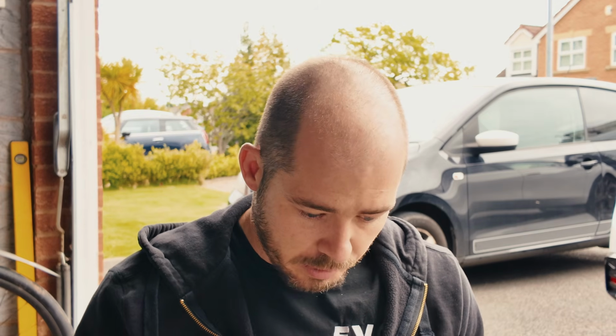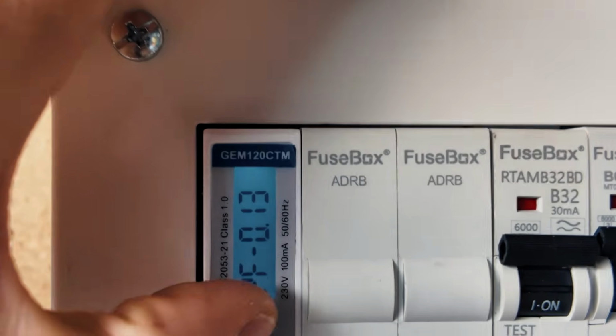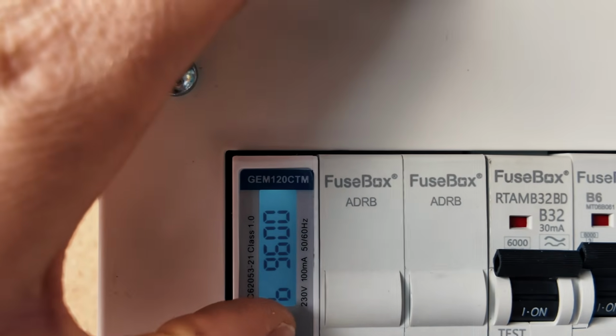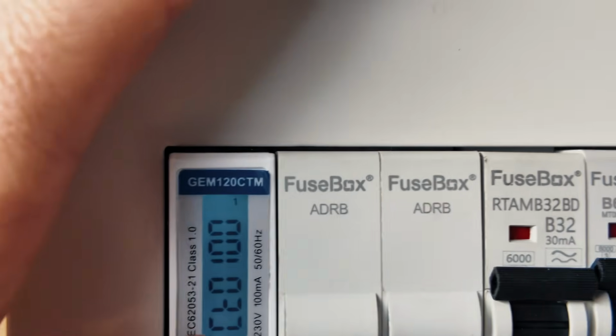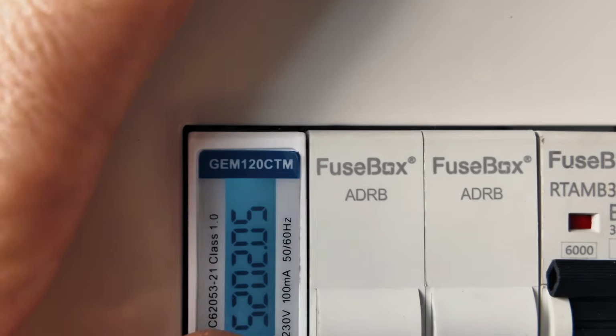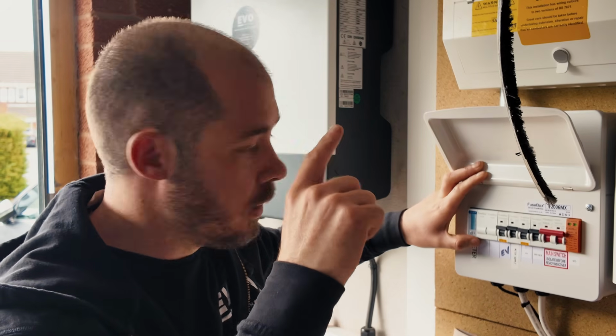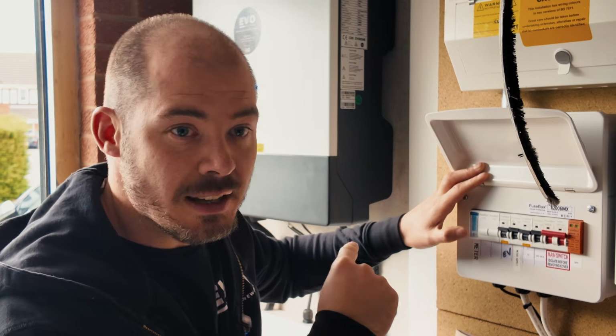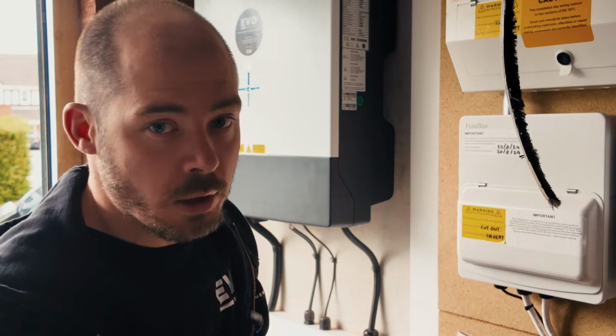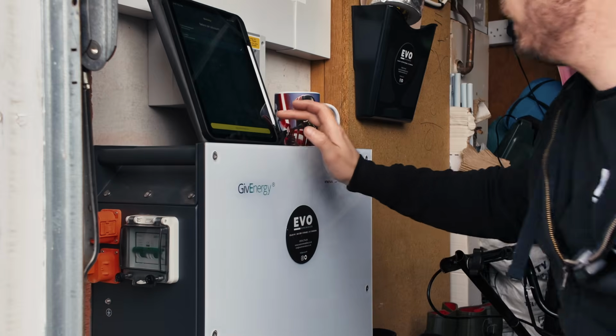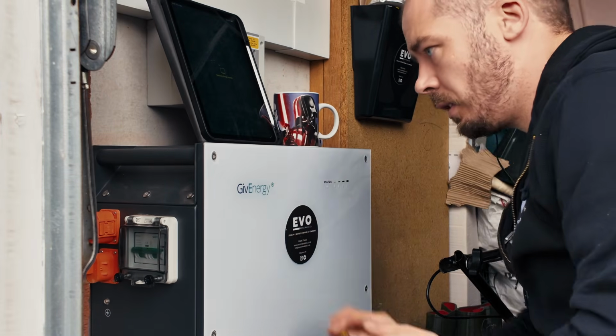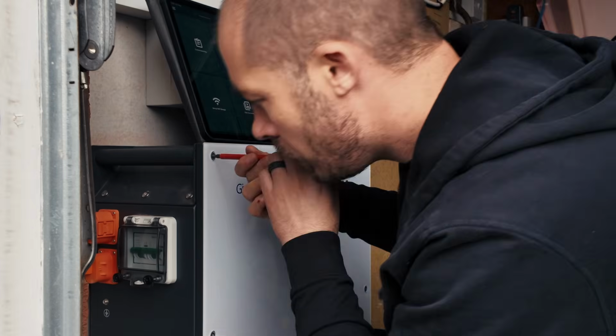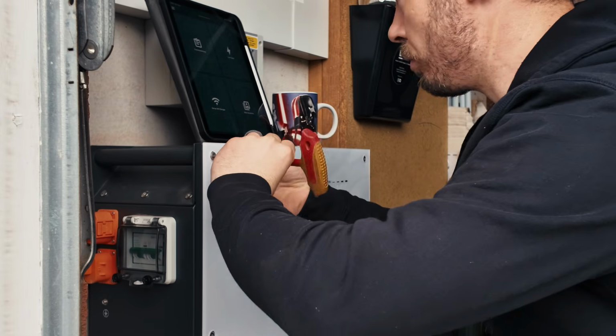Let's have a look on the app and see how it's actually doing. So we can see from the Modbus, it is actually registering import and export. Customers put the kettle on and I could just see that go up, and I can see it drop down now. So I know the Modbus is working. I'm going to check the CT positioning just in case anything has changed there, but I still suspect it's going to be a battery issue. Let me check the CT and then we'll open the battery up and take a look. Right, so first of all, let's get this cover off and check some voltages on the battery.